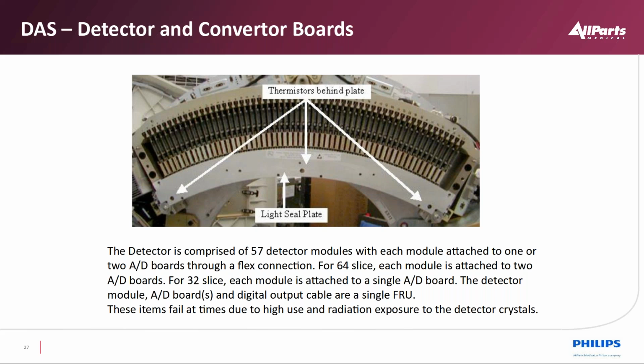We have calibration vectors for every one of these. This detector has 64 rows in it, with this number of channels. With regards to that, we have a lot of cal data. So when one of these modules is changed, we actually have to recalibrate the machine.